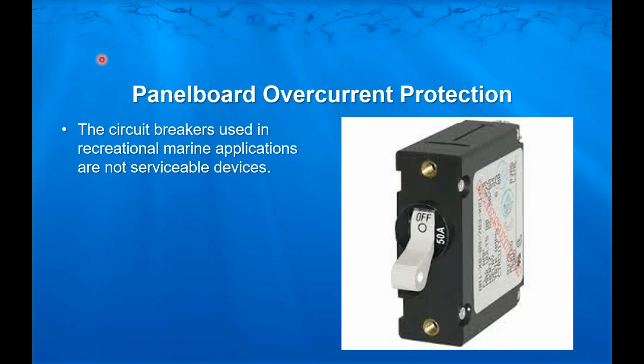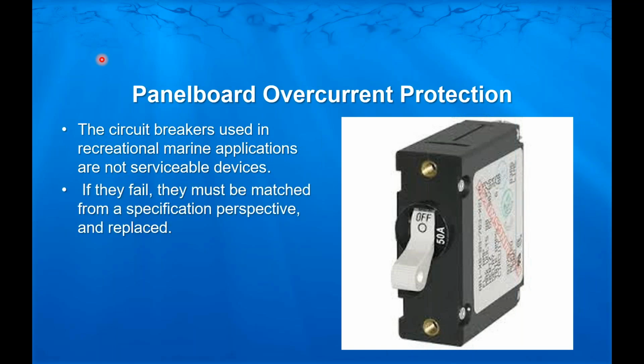As far as breakers, even if you do hopefully use marine grade products, they are not serviceable devices. If they fail, they've got to be matched to the specifics of the circuit. Don't assume that it was right in the first place. Make sure you know what that thing is powering, what it should be. It may be correct, it may not be correct, but don't put the same breaker back just because that's the size that was there. Confirm what that circuit actually is. But you've got to replace it. Do not attempt to repair circuit breakers.